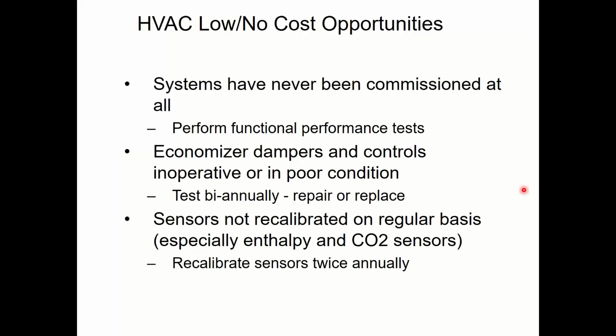Calibrating sensors is pretty important. Some sensors are pretty good, like temperature sensors. Most of the HVAC temperature sensors are thermistors. Thermistors tend to not drift. They're either good or they're bad, so they're pretty easy to check. Enthalpy sensors, which we'll use with the economizer, and CO2 sensors, which we talked about last week for demand control ventilation, have historically drifted badly. The new ones are not as big of an issue. We switched to solid state on the enthalpy instead of the old horsehair, which is fantastic. Horsehair is not fantastic, solid state is. And on CO2 sensors, we have that automatic calibration routine that we talked about last week. So the reliability of both of those has dramatically improved in the past 10, 12 years.